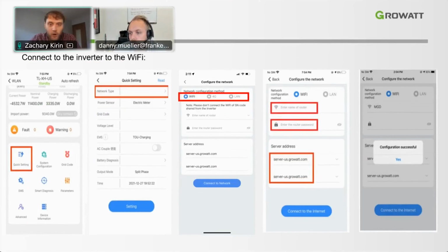So the very first step when logging into the inverter screen then will be quick settings, network type, and then they'll be able to select what network configuration they need. That'll be either LAN or Wi-Fi. Important to note, and this should be on every screen, no matter where you get the inverter from, the server address should always say server-us.growatt.com. I've never seen it not say that, but it is very important that it does say that for proper Wi-Fi communications, for proper communications with our server.